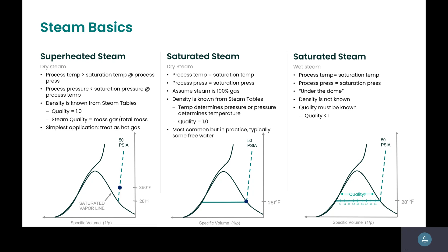But when we talk about steam, you also have to talk about wet steam as well. In an ideal world I wish everything was completely dry, but due to insulation and other reasons, steam will be wet. At this point it's under the dome, we look at specific volume versus temperature, and quality really ranges anywhere from 1 to 0. Typically 0.9 or better is what you want to see from the steam measurement overall. But naturally you have to talk about wet steam because that's real life, and we'll talk a bit more about it, since it's one of the challenges in steam measurement.